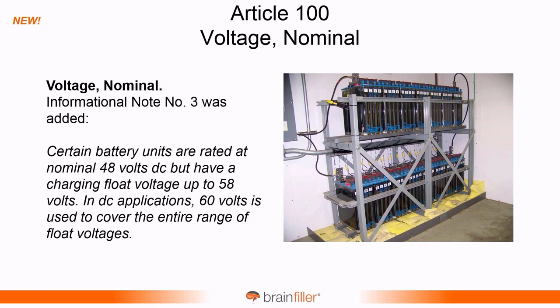Nominal voltage. This is about DC voltage. It's understood that certain battery systems are rated 48 volts nominal, but they can have a float charge up to 58 volts. So in DC applications, 60 volts is used just to cover the entire voltage range. So that was a new informational note.